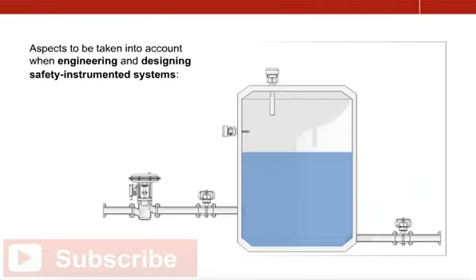At the end of this module, we would like to summarize the information provided. Before engineering a safety-instrumented system, its exact task must be defined. Based on this definition, the architecture can be determined, particularly concerning the required redundancy, above all in final elements. Additionally, it can be determined how this redundancy is to be implemented. Component selection is based on the process.